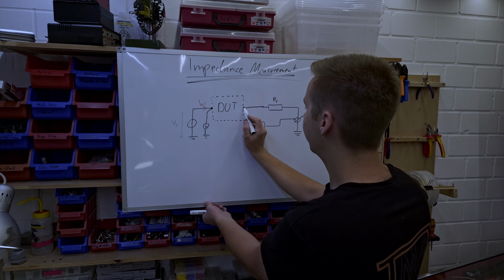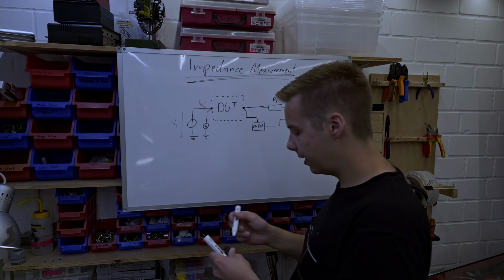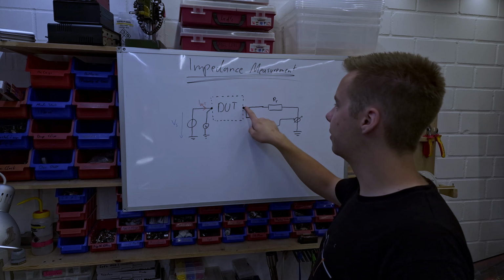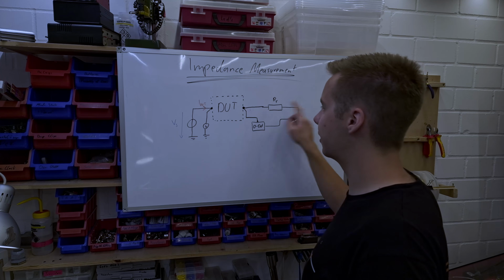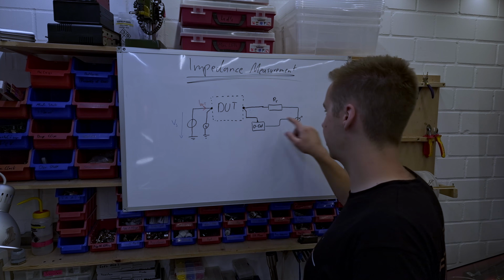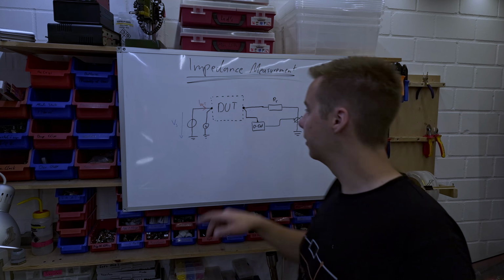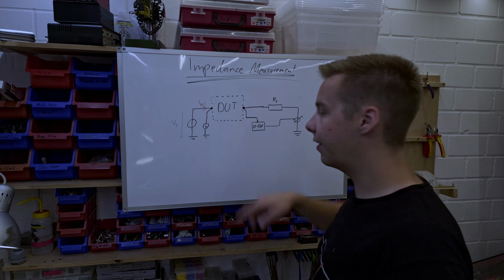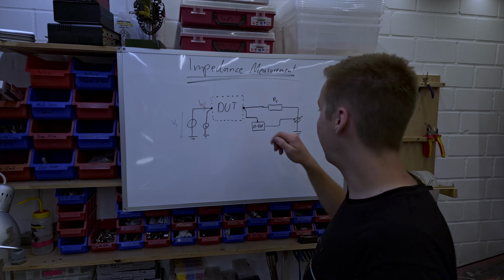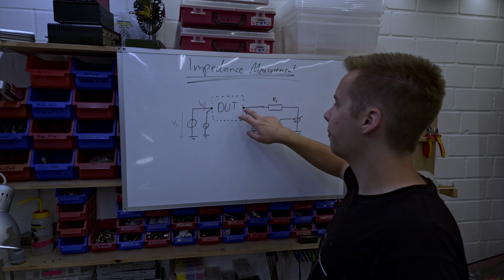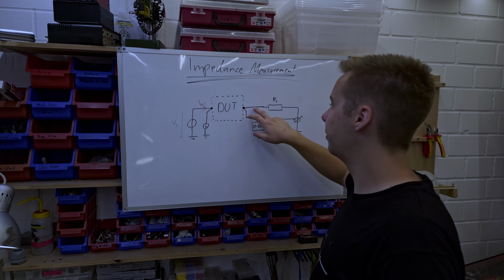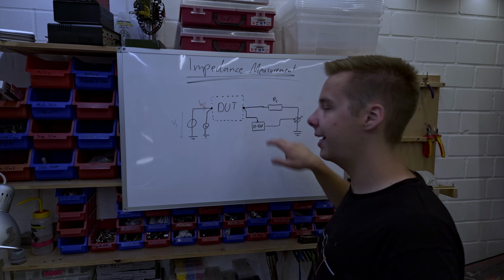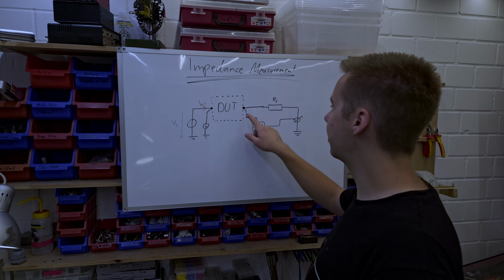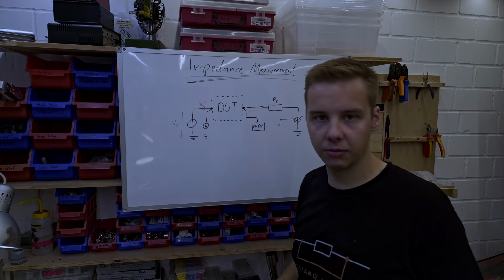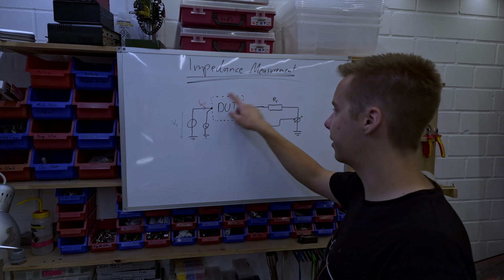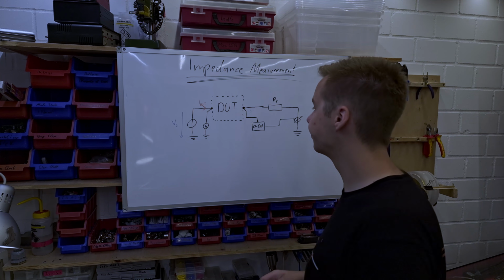So right there. Now all of the current that goes into this cable here obviously has to come out here, so it doesn't matter if we have the second voltage source connected somewhere far away from this, but the voltage measurement happens exactly at the device under test. So although we are actually adding the cable resistance or cable impedance to our test impedance, we could calibrate this out because cables stay the same and only the device under test is actually measured again.